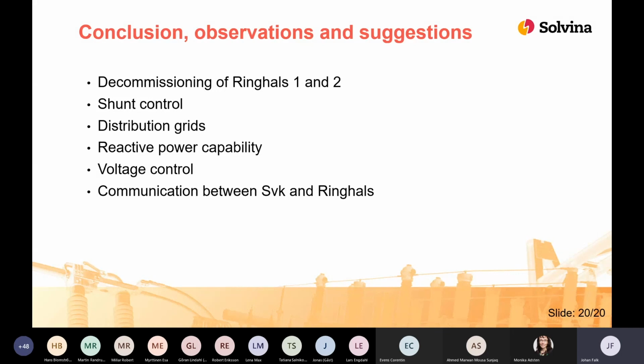It's quite hard to make predictions on this topic, since there will be changes in power flow, changes in short circuit power, and new equipment will be installed. So it's a hard topic to make predictions on. And finally, the communication between Ringhals and Svenska kraftnät could potentially have room for improvement. This is since, as I said, the set points for the generators are only changed after Svenska kraftnät asks Ringhals to change the set points, and this doesn't happen very often.